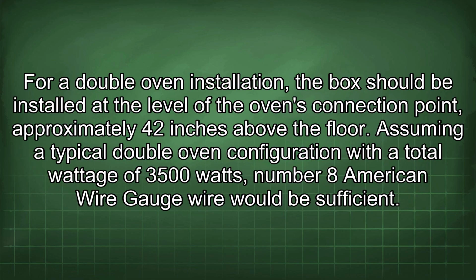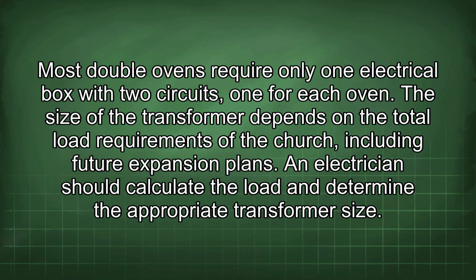For a double oven installation, the box should be installed at the level of the oven's connection point, approximately 42 inches above the floor. Assuming a typical double oven configuration with a total wattage of 3,500 watts, number 8 American wire gauge wire would be sufficient. Most double ovens require only one electrical box with 2 circuits, one for each oven.